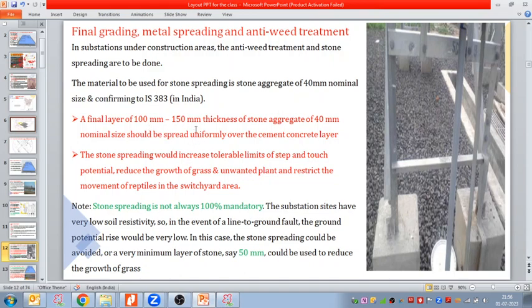For the stone spreading, we can refer to the earthing standard, which is IEEE 80. As per IEEE 80, a layer of 100 mm to 150 mm thickness of stone spreading of 40 mm nominal size should be spread uniformly over the cement concrete layer. This is also defined in IEEE 80. And why is stone spreading required in the substation? As you have all also been told, stone spreading would increase the tolerable limits of step and touch potential.